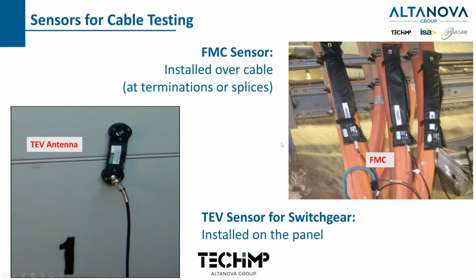Sometimes locations won't allow their switchgear to be opened for various reasons. If that's the case, we'll utilize a TEV antenna that clamps on, or it's actually magnetic, and sticks onto the switchgear, and then we're able to pick up any partial discharge going on inside the switchgear. And sometimes we're not able to get around the ground, or for whatever reason, the splice or the cable, so we also have a different type of sensor. It's called a flexible magnetic coupler, and that goes on either the splice or the cable. So they're just all different forms of antennas, picking up RF signals in the circuit.